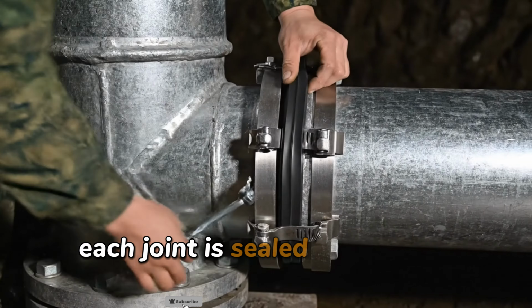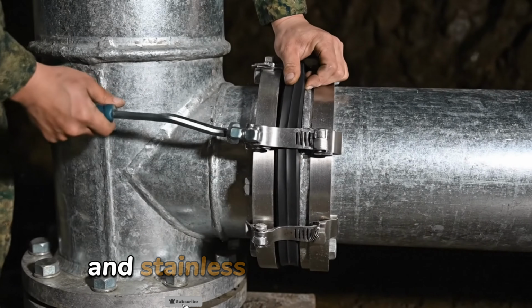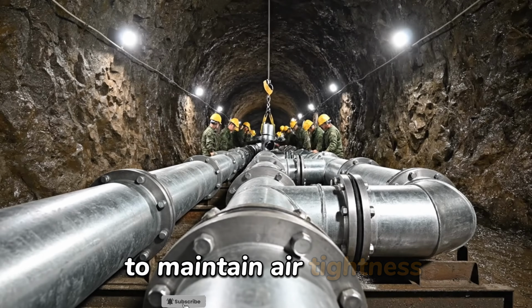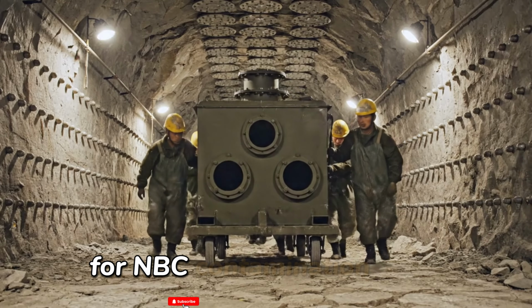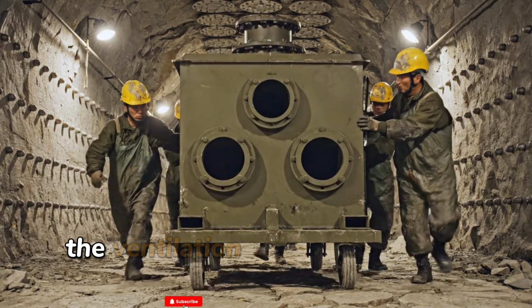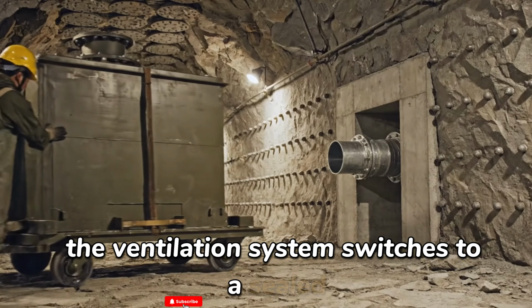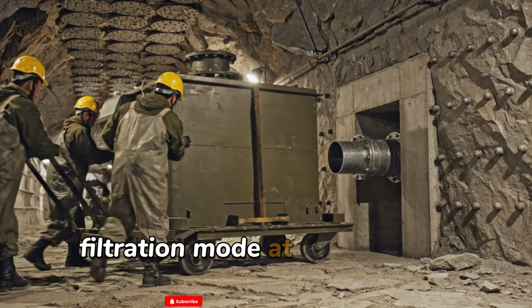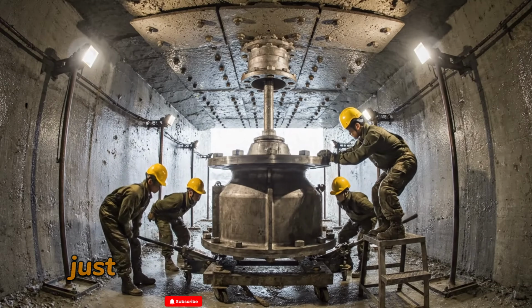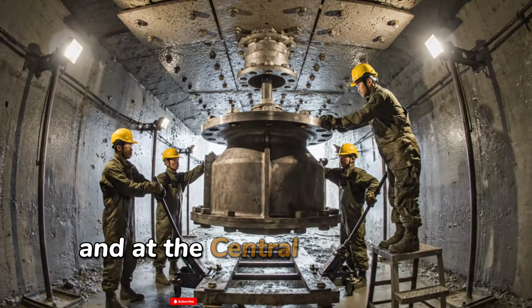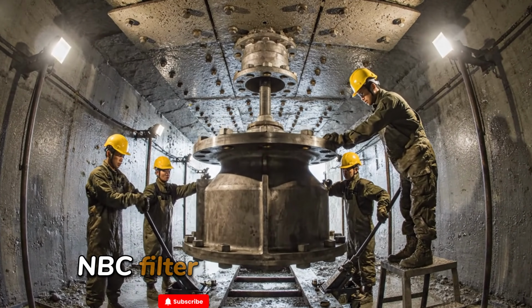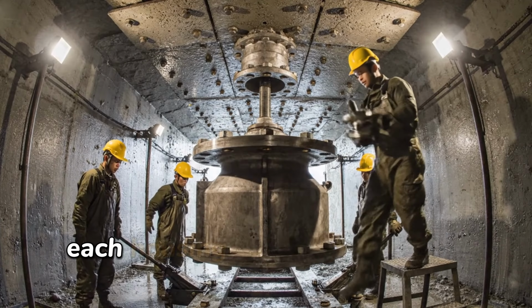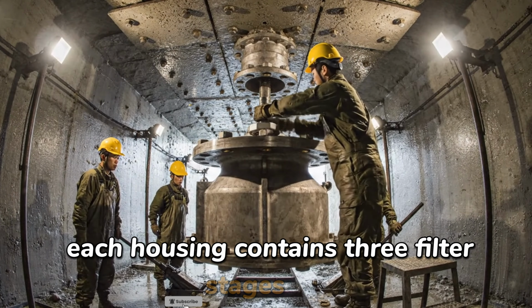Each joint is sealed with a butyl rubber gasket and stainless steel band clamp to maintain airtightness. For NBC contamination events, the ventilation system switches to a sealed filtration mode. At 2 points in the system, just inside the mountain entrance and at the central air handling unit, NBC filter housings are installed. Each housing contains 3 filter stages.